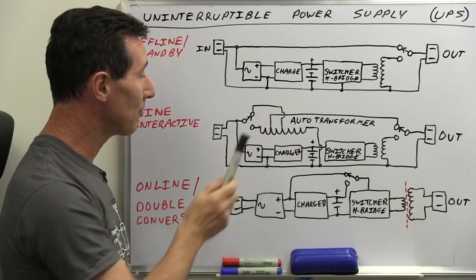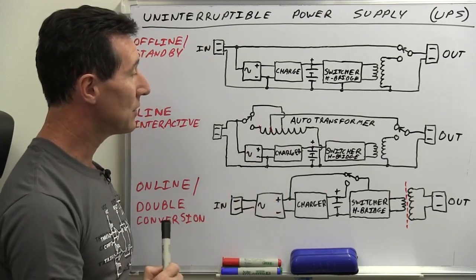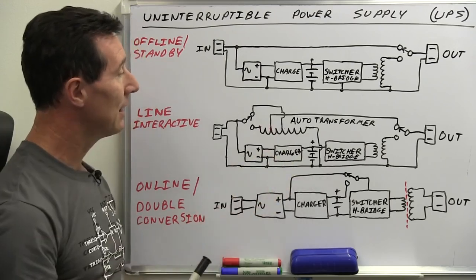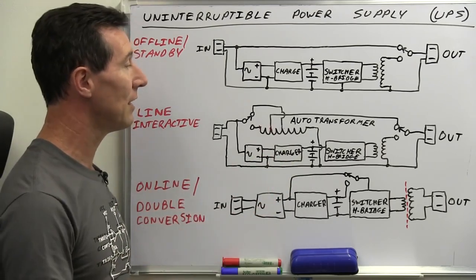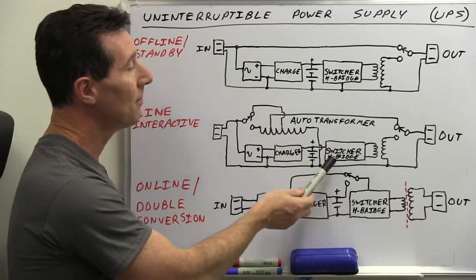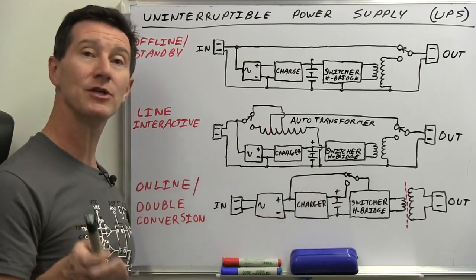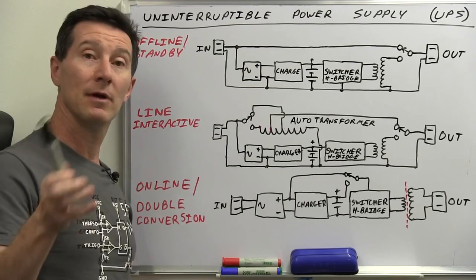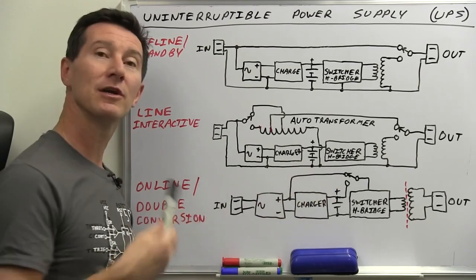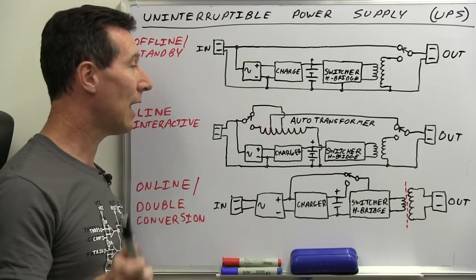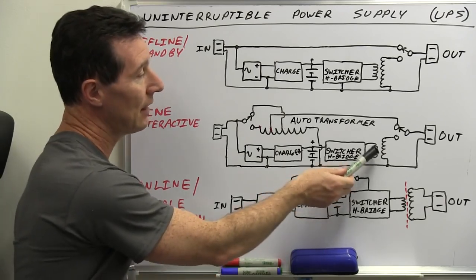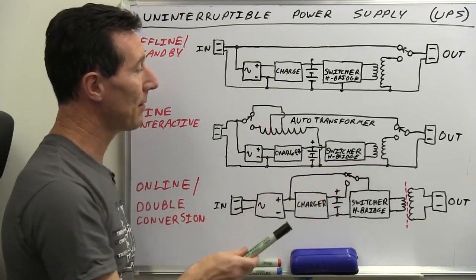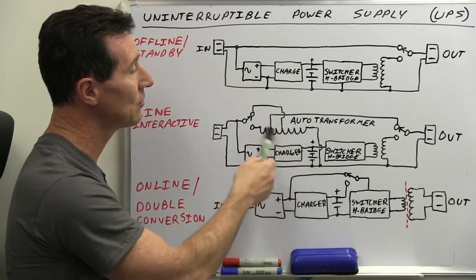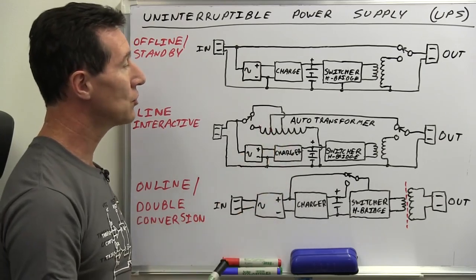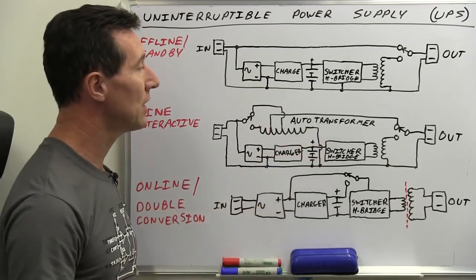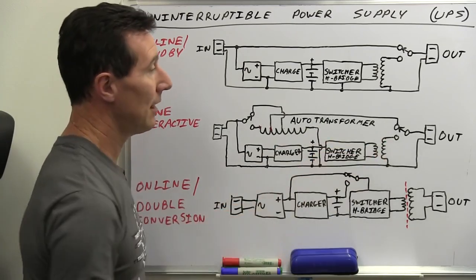Then we're going to have our rectifier, our charging circuitry, our battery bank - in the case of this one, I know it's 48 volts. Then we're going to have our switcher, most likely an H-bridge configuration, though we won't know until we actually take it apart. That H-bridge is going to have 4 large MOSFETs driving the primary side of the step-up transformer, which could possibly be integrated into the main auto transformer with another tap. We'll see when we open the thing.